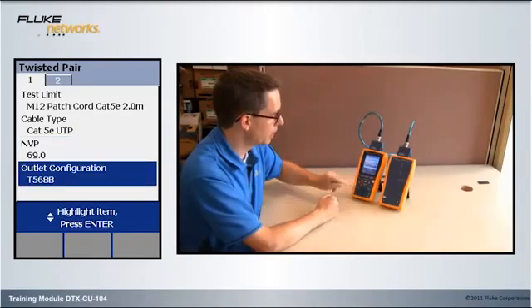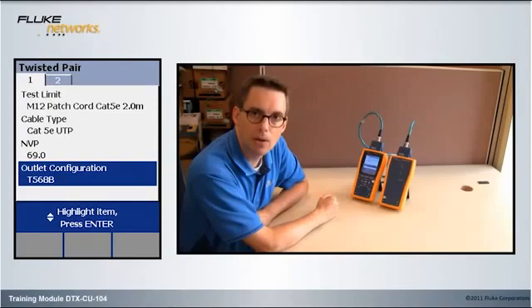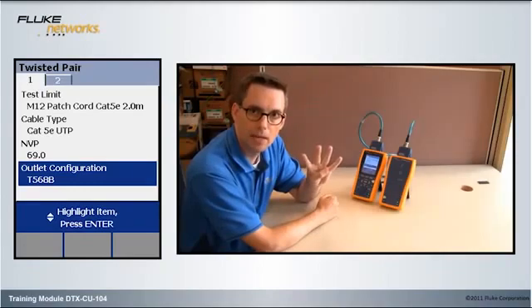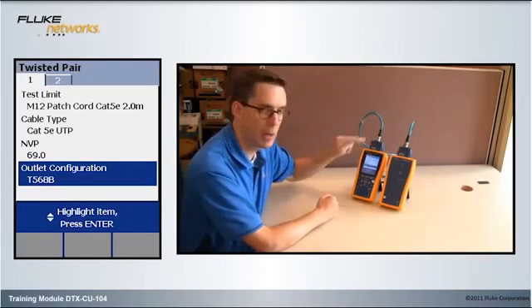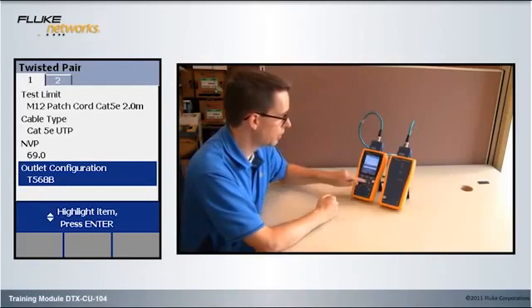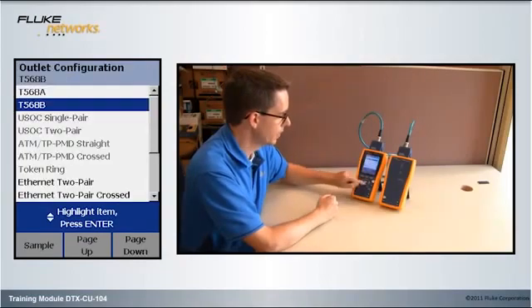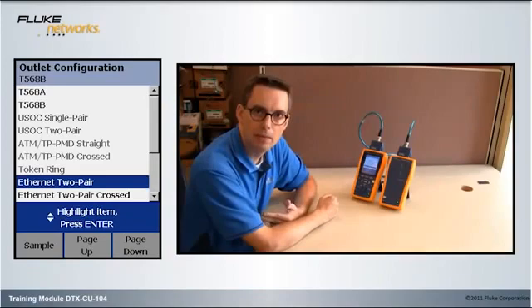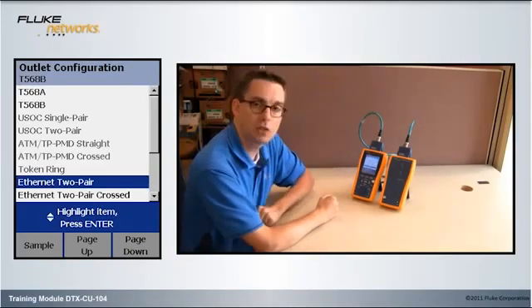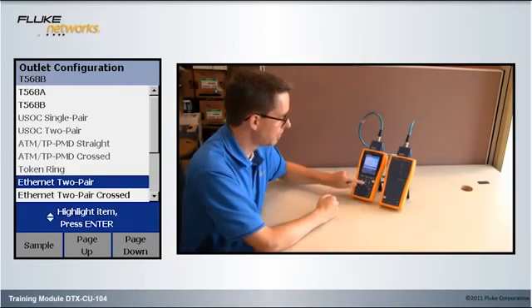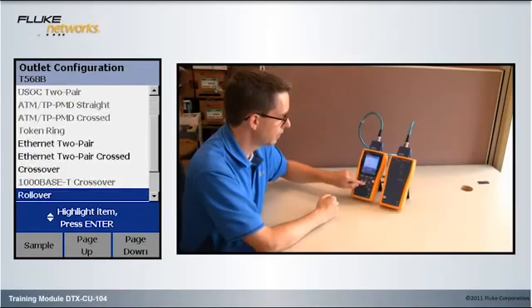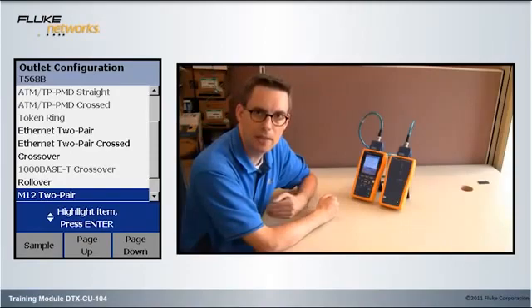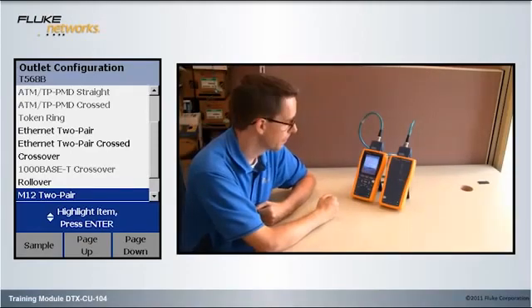The final setting we need to be concerned about is Outlet Configuration. It's currently set to T568B. That's a four-pair standard, and we've only got two pairs in the cable here. So, we need to change that. I could select Ethernet two-pair, because it's Industrial Ethernet and it's two pairs. But I'm going to go down until I find M12 two-pair. We put that in there as an additional aid to help people find the right Outlet Configuration.